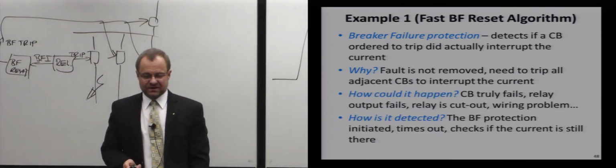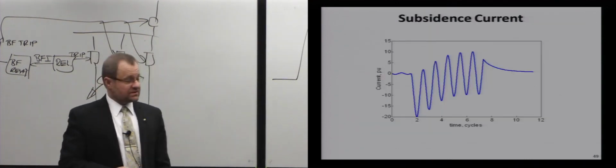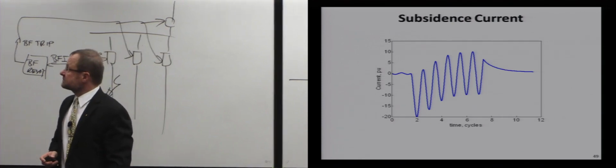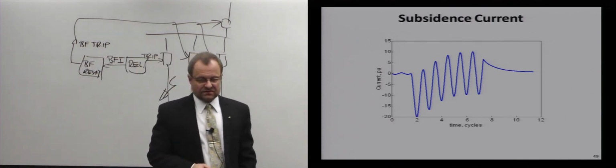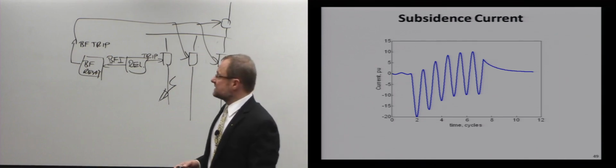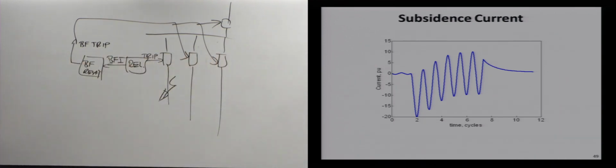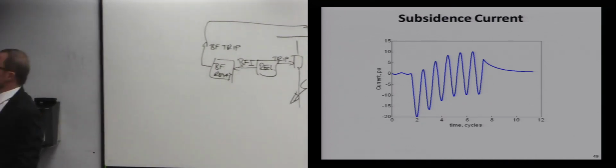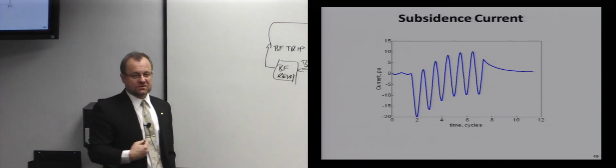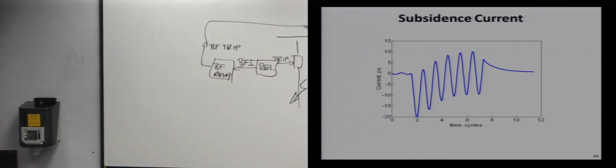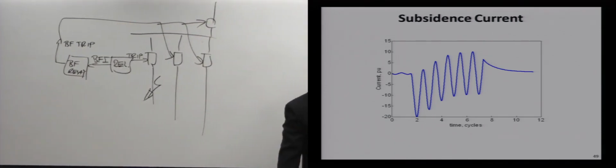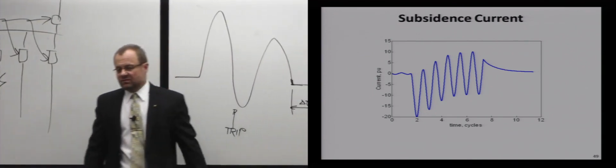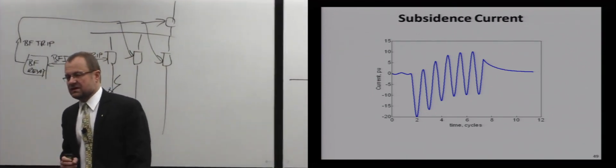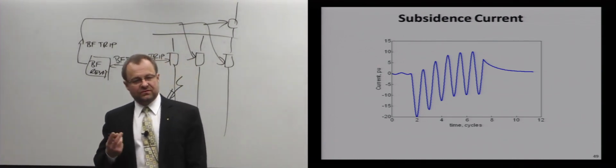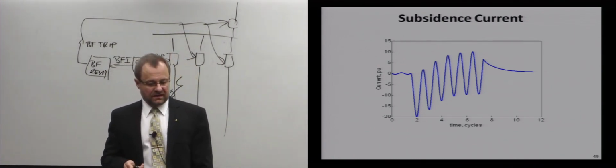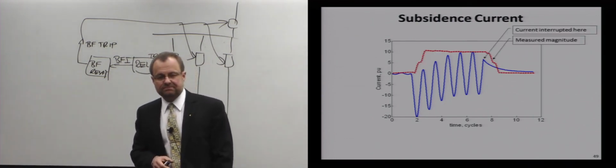It sounds very simple, right? This is the problem. The problem is that in reality, what will happen is that current transformers may saturate. So when the primary current is interrupted, it's interrupted here. The secondary current, the current that actually relays measure, is not 0. It's not going to become a nice flat 0 like here, right? So what will happen if we measured this current with something like a full cycle Fourier algorithm? This is what we will see.